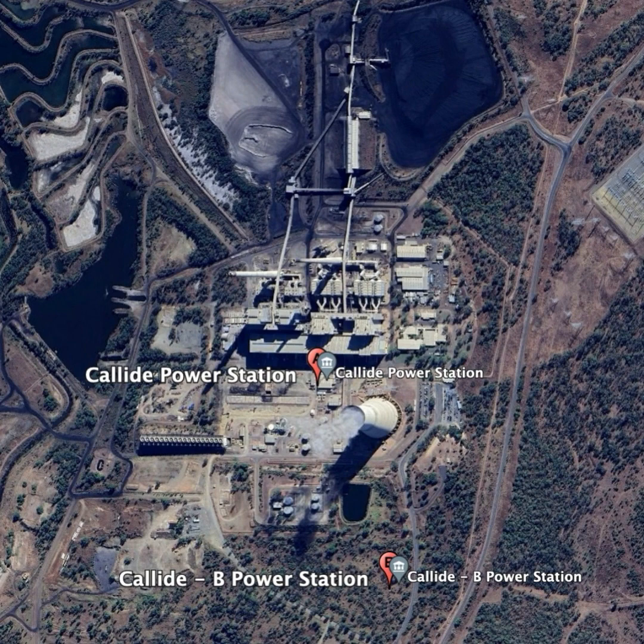Since the generator circuit breaker couldn't trip, the generator remained connected to the grid, and without an energy source to drive the motor generator set in forward generation, it shifted to forward motoring. Essentially, the generator became a huge asynchronous motor. Since there was no rotor excitation, it was being driven by grid power, now drawing power from the grid instead of supplying power to it.